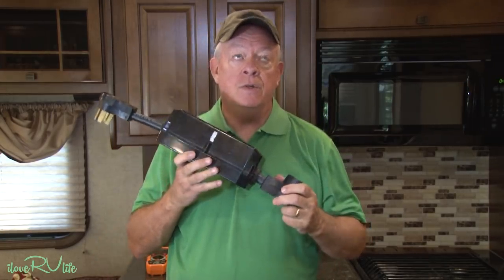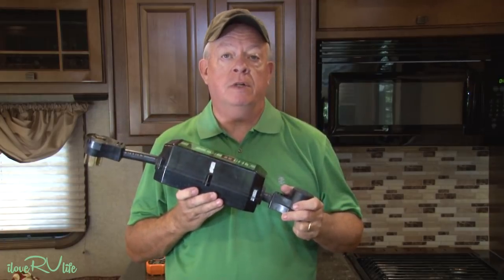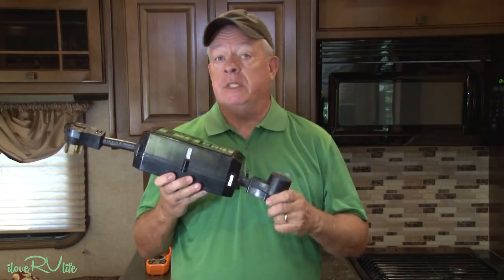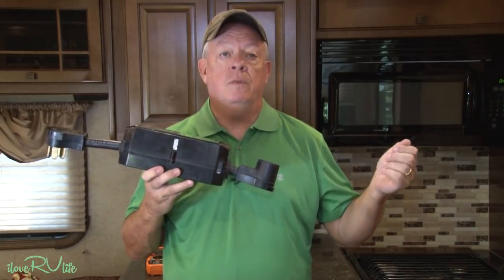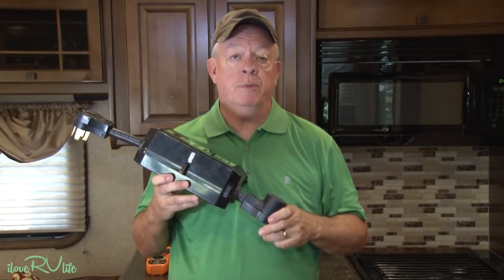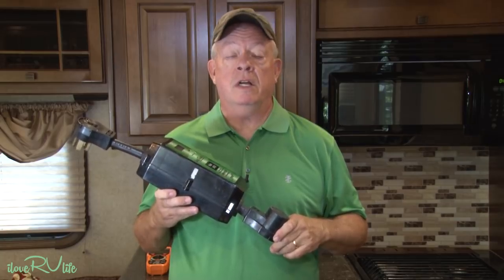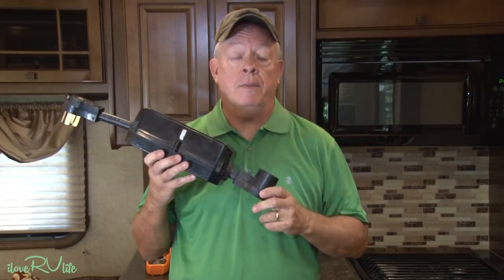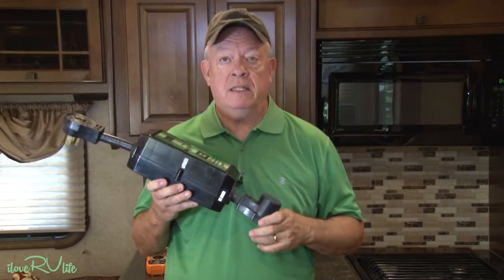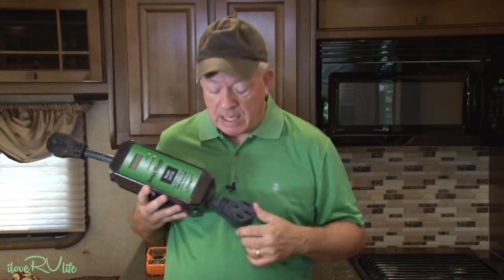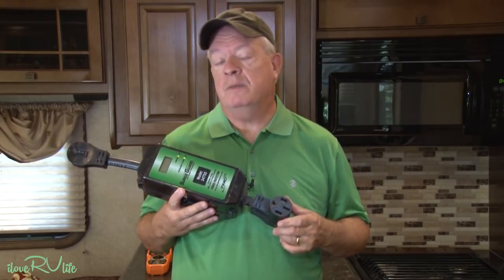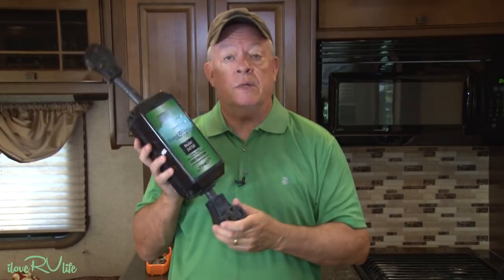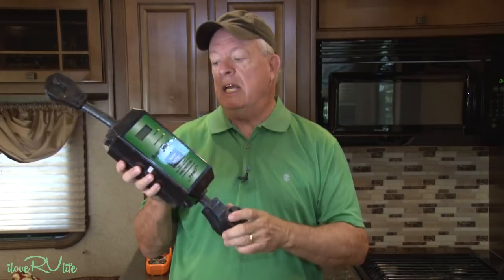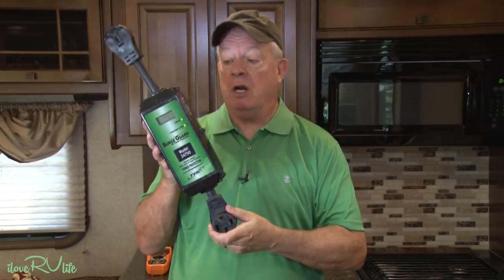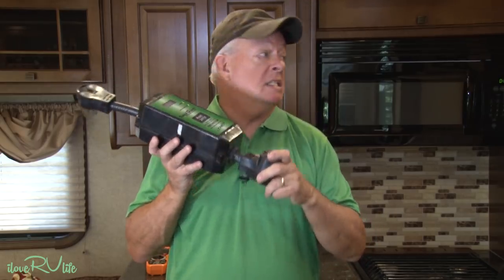We've had two instances of this. One was when we pulled into a campground down in Panama City, and it was hotter than blue blazes that day. Everything was working well, both air conditioners running fine, everything fantastic. Then boom, all of a sudden one of the air conditioners quit, and just a microsecond later all the power went off inside the camper. I thought, uh-oh, we blew a fuse, let me go check. I'll show you how I use my digital voltmeter to test that in just a few minutes. But what I found was indicators on this unit saying we had a fault. The voltage on one leg had gone away, and in the process the surge guard automatically turned the power off to the camper and saved every bit of my electronics.